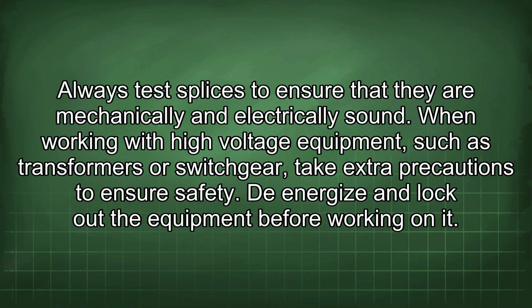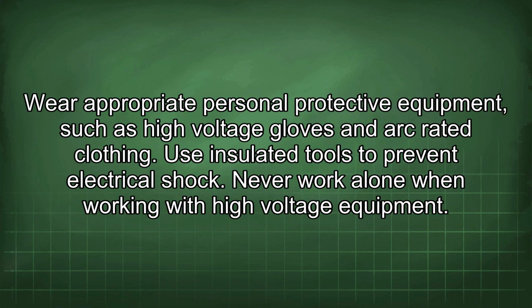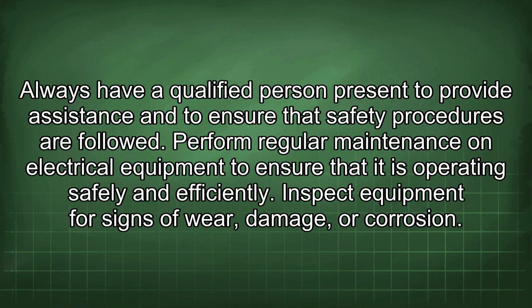When working with high voltage equipment, such as transformers or switchgear, take extra precautions to ensure safety. De-energize and lock out the equipment before working on it. Wear appropriate personal protective equipment, such as high voltage gloves and arc-rated clothing. Use insulated tools to prevent electrical shock. Never work alone when working with high voltage equipment. Always have a qualified person present to provide assistance and to ensure that safety procedures are followed.